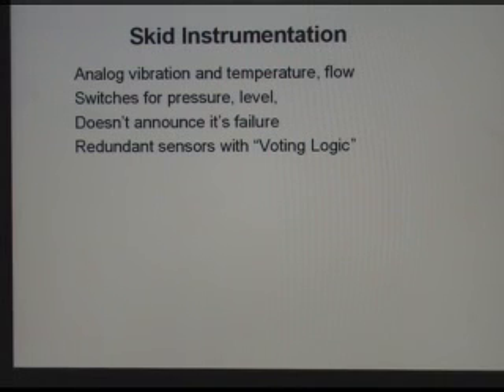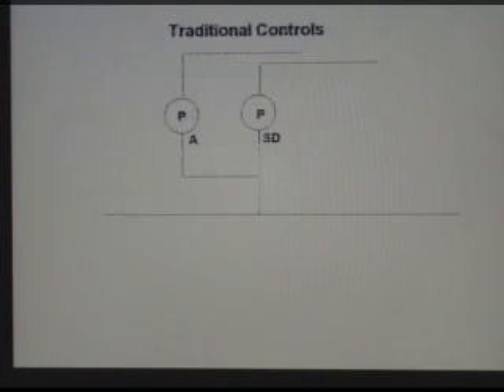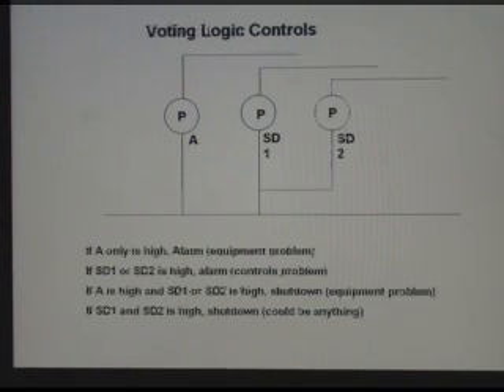So the solution was, why don't we just put in redundant sensors with voting logic? We have redundant PLCs, we can put redundant sensors on as well. And so, up until that point, you had 2 pressure switches, one for an alarm and one for a shutdown. This one would go off, you get an alarm, that one would go off, the machine is shut down, pretty straightforward. So now they wanted voting logic controls.